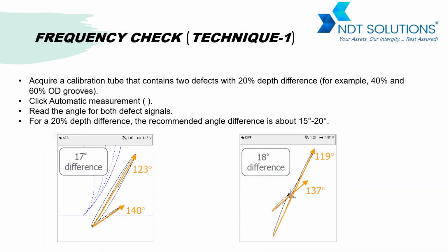So there is no need to apply any formula. If you have used MS5800, MultiView or Ectane equipment, whenever we start making the wizard setup, what we generally do is give the value of the thickness and the material, and the equipment suggests the optimized frequency itself. On that frequency, we just calibrate our calibration tube and start doing the inspection.